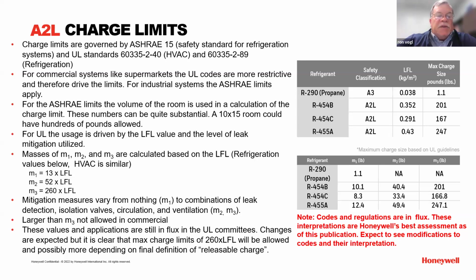You're in the HVAC business doing a lot of light commercial and residential work, putting 3-ton units in homes regularly - there's a lot of volume in a typical home. Now you get called to a small computer room, 10 by 10, and you want to hook up that same 3-ton unit. Most likely you'll be out of compliance because of that small space, even though you need 3 tons for the high heat load from the computers. So you see where I'm going - you have to be aware of what you're doing and using, and make sure you're compliant. This falls back on the installing contractor to be aware of it and do the right thing.